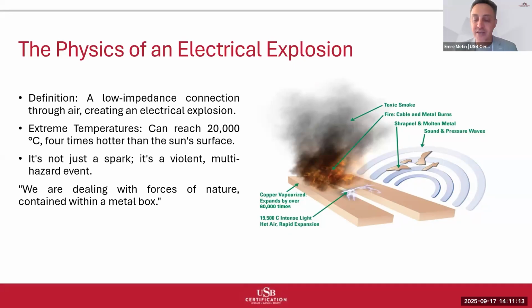The diagram you see here illustrates the multiple energy release mechanisms. We have copper vapor expanding by 67,000 times its original volume. We have molten metal droplets ejected at high velocity. We have intense light across the entire spectrum, from infrared through visible light to ultraviolet. We have pressure waves traveling at acoustic velocities. This is why I use the phrase forces of nature contained within a metal box.